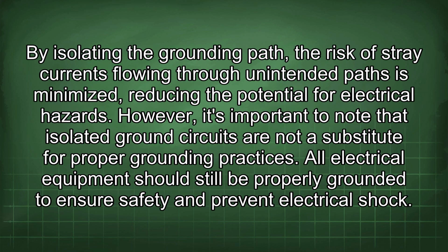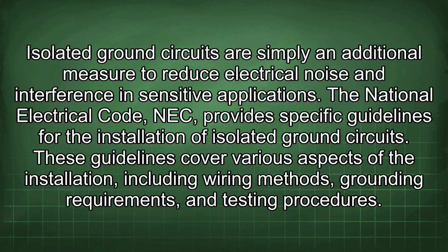By isolating the grounding path, the risk of stray currents flowing through unintended paths is minimized, reducing the potential for electrical hazards. However, it's important to note that isolated ground circuits are not a substitute for proper grounding practices. All electrical equipment should still be properly grounded to ensure safety and prevent electrical shock. Isolated ground circuits are simply an additional measure to reduce electrical noise and interference in sensitive applications.